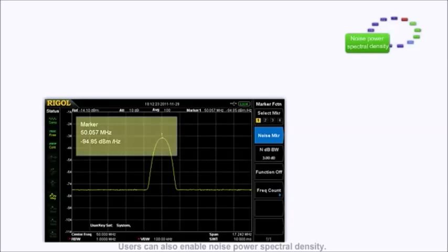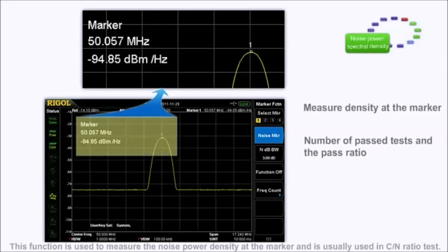Users can also enable noise power spectral density. This function is used to measure the noise power at the marker and is usually used in carrier-to-noise ratio tests.